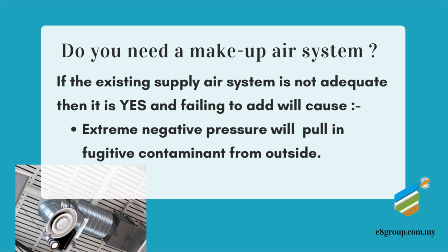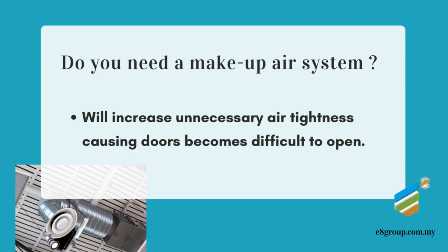Just because you decide not to add makeup air or supply air doesn't mean nature is not going to pull the air in, because you are running the room under extreme vacuum, based on 100% exhaust ventilation. So air is going to come through the gaps under the door, from the window seals, and so on. That is why it's important to maintain this. The fan curve has probably been designed to operate based on the static pressure and the flow rate, but the fan is going to struggle because there's no air. So imagine this is what's going to happen to the fan which runs under 100% vacuum or without makeup air.